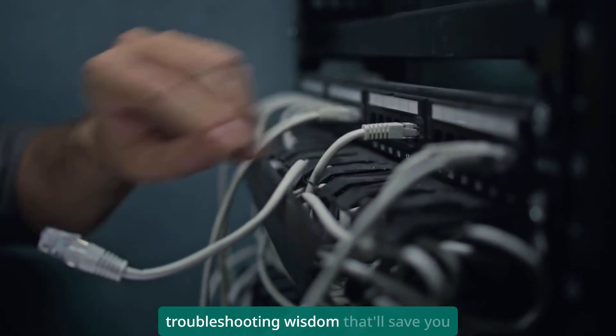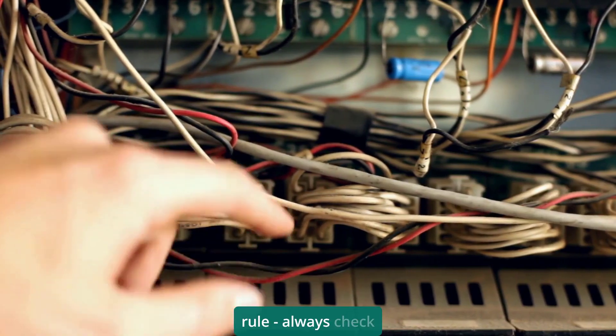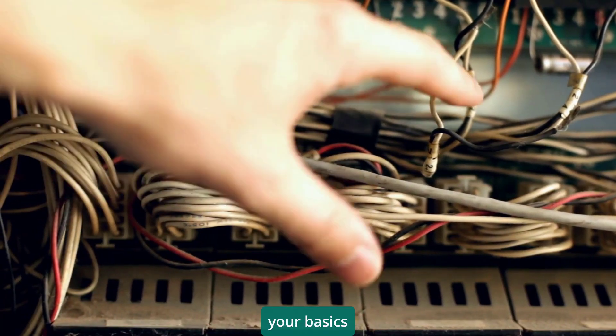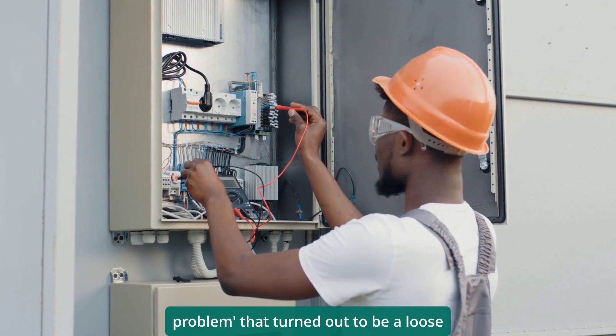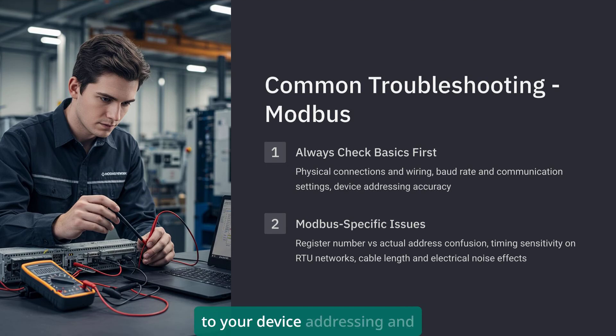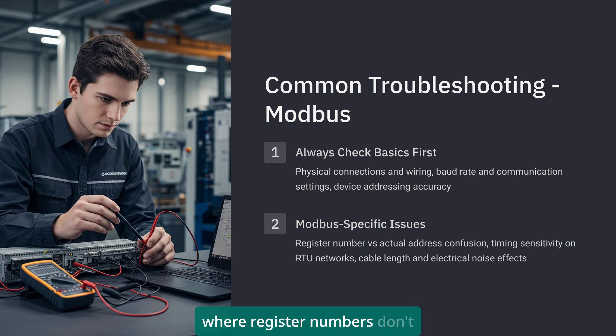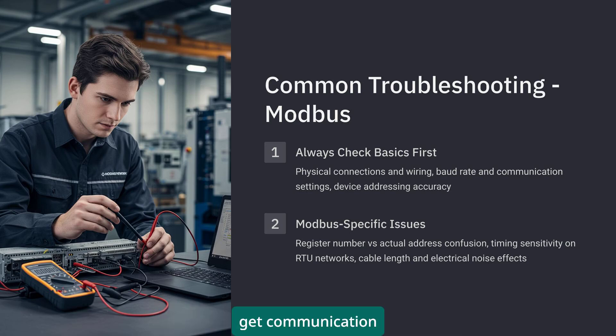Now let me share some troubleshooting wisdom that'll save you hours of headaches. First rule: always check your basics first. I can't tell you how many times I've been called out for a protocol problem that turned out to be a loose wire or wrong baud rate setting. For Modbus, pay attention to your device addressing and register mapping — Modbus has a quirky thing where register numbers don't always match the actual addresses used in the protocol. And remember, Modbus RTU is very sensitive to timing; if your cable runs are too long or you've got electrical noise, you'll get communication errors.